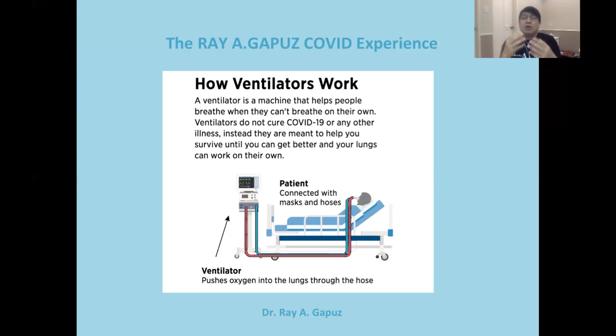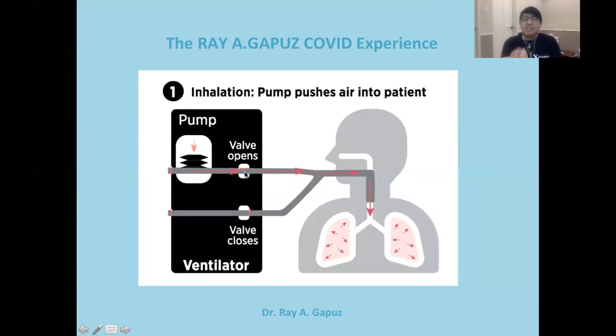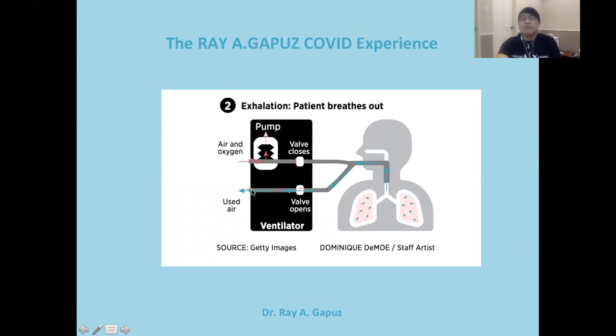Your ventilator pushes oxygen into the lungs through your oxygen delivery system, through a hose. During the inhalation phase, the pump pushes air into the patient, and of course, the valve that facilitates the exit of air from the patient is closed. So the valve that facilitates the entry of air is the one that's open. Now, what happens during the exhalation phase? As the patient breathes out, the valve that pushes air closes, and then the valve that facilitates the exit of air from the patient opens. So it's just a closed-open mechanism.